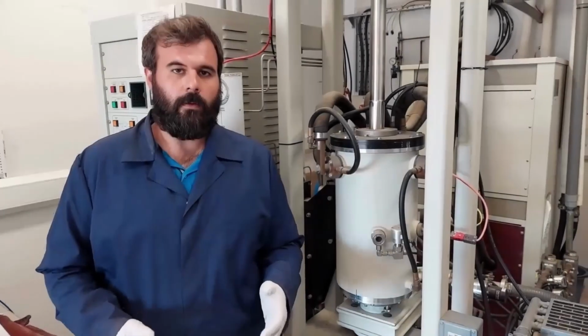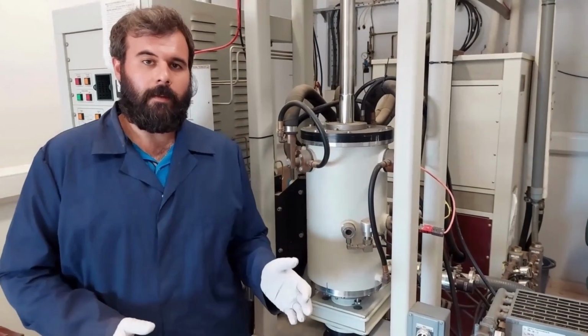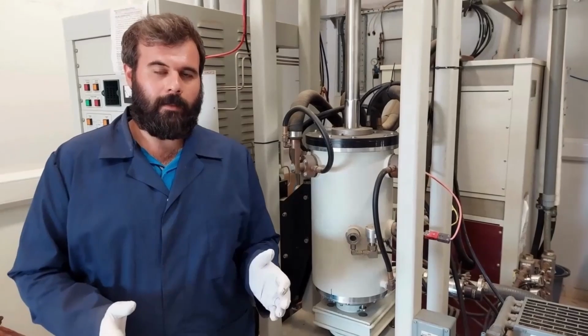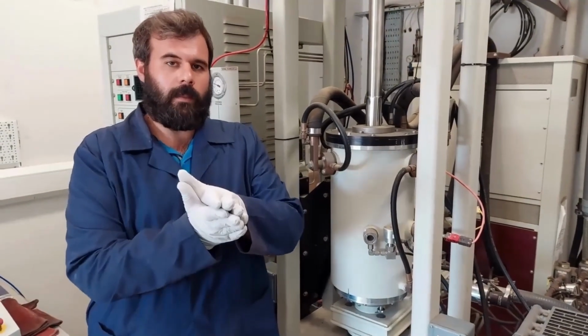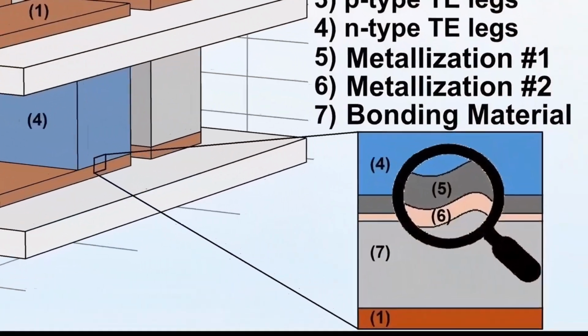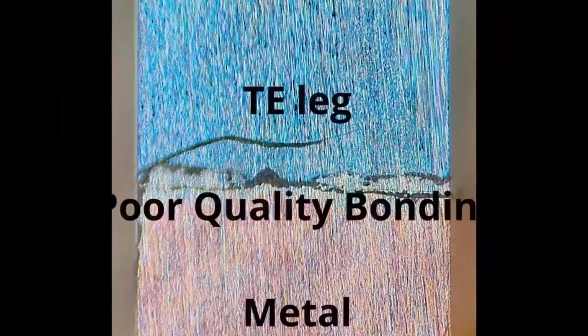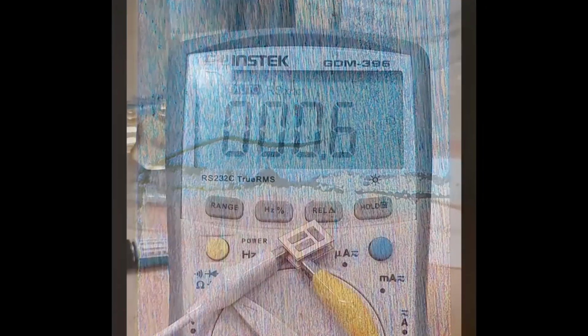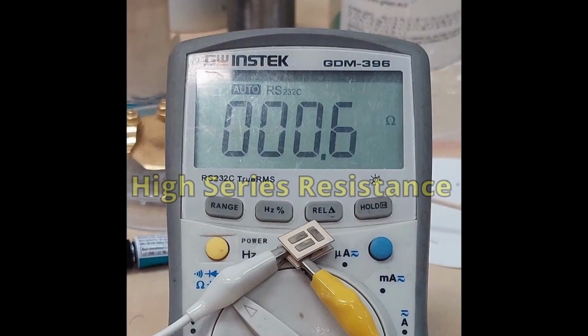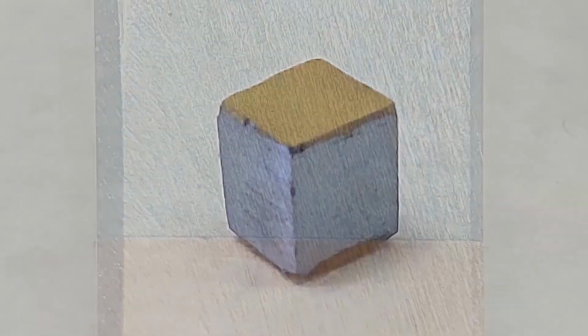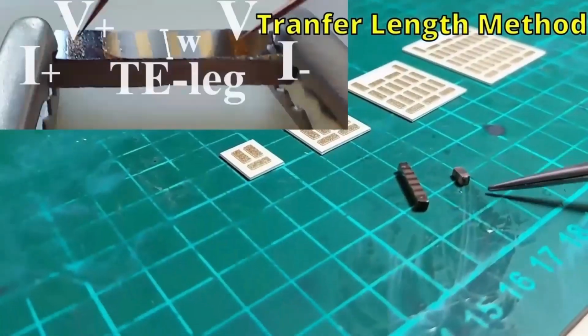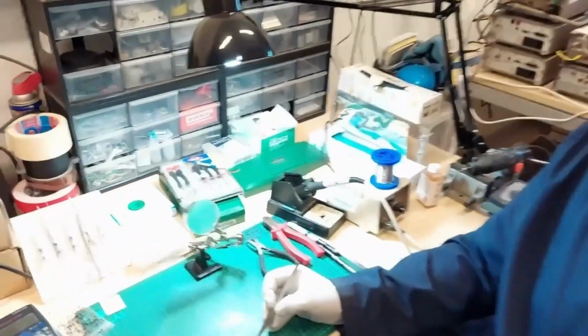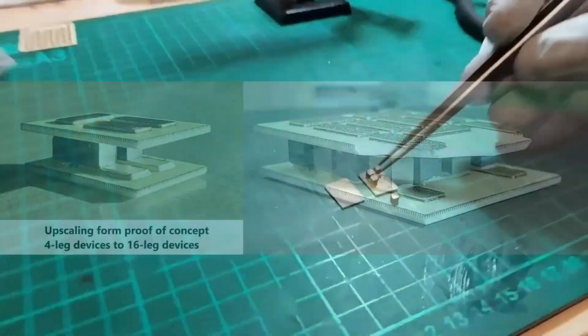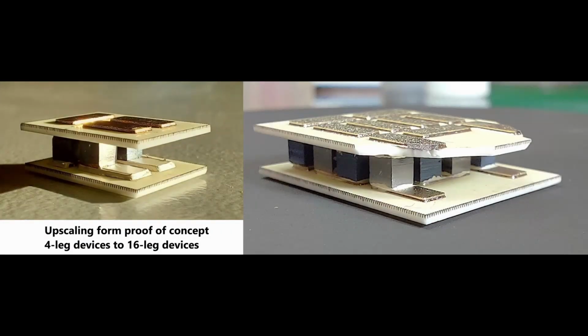A key component of a thermoelectric module is the thermal bonding between thermoelectric legs and the metal interconnects of the ceramic circuit board. Poor quality bonding would lead to high electrical and thermal contact resistances, which can be detrimental for the module's performance. As such, the contact resistance of the metallization and bonding are tested through the transfer length method and the scanning probe measurement respectively. Finally, all the components can be assembled and thermally bonded for the fabrication of a thermoelectric module.